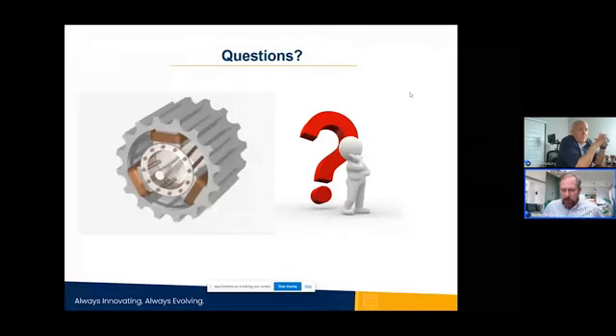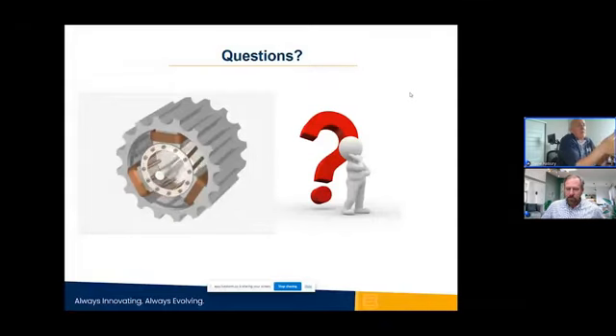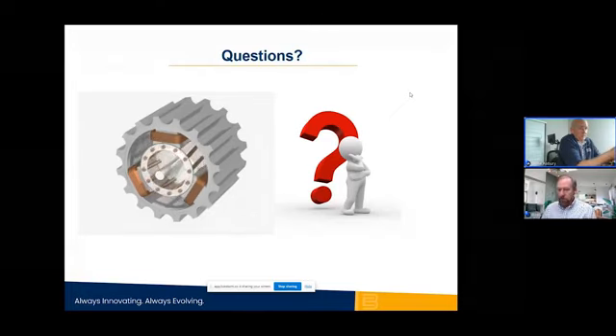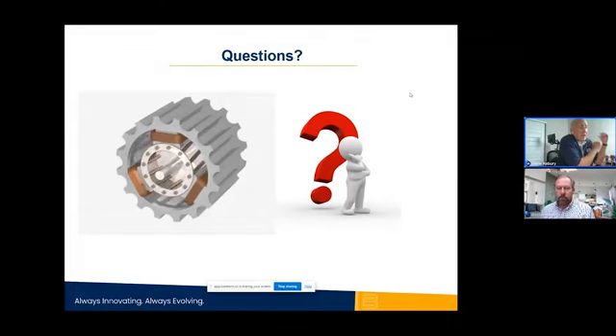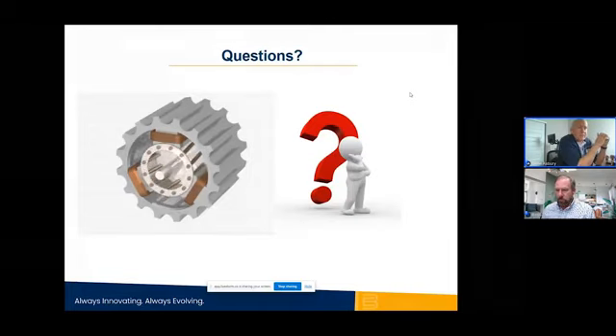Okay. One more. For how long can the 250N be at 20 amps continuous? Yeah, within reason. If you put it outside and it meets all the environmental regulations that we set forth in our manual, then you're fine at 20 amps. If you put it in an air conditioned room at 25C, you might be able to get a couple more amps out of it.